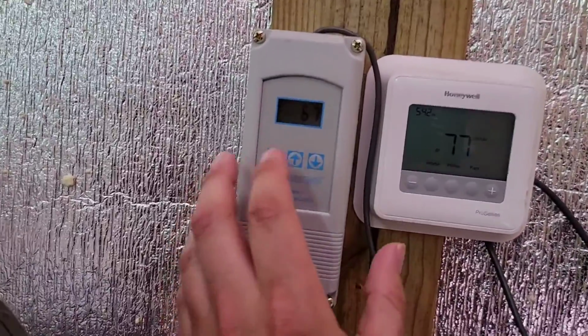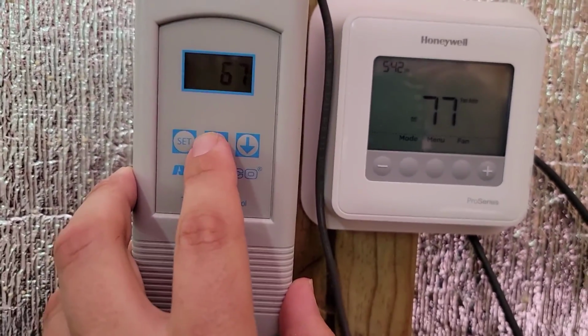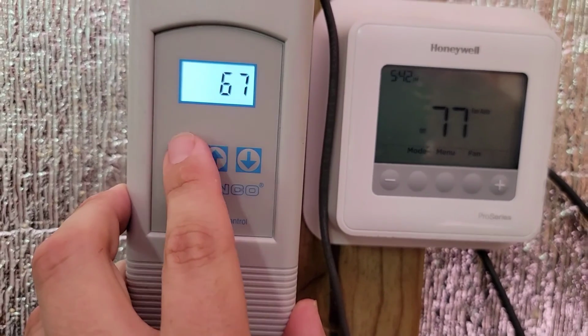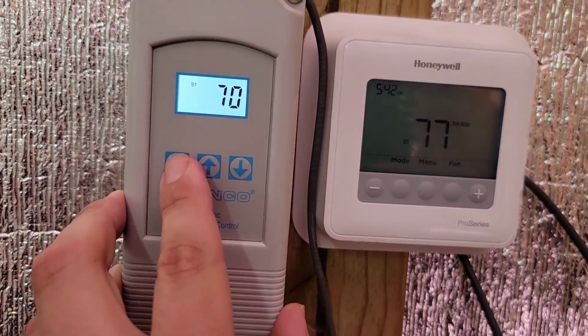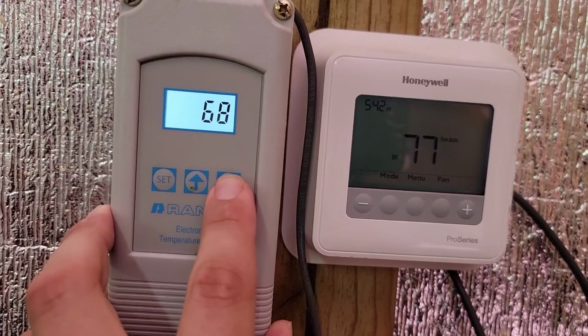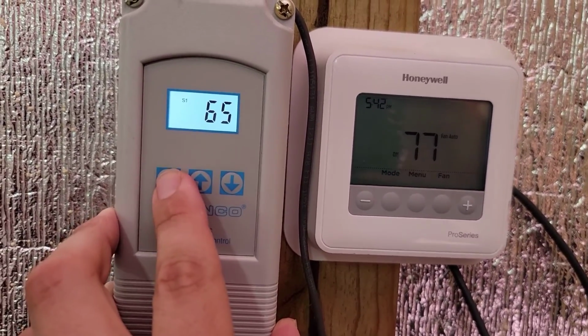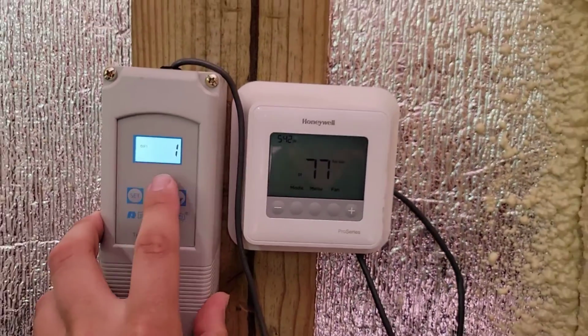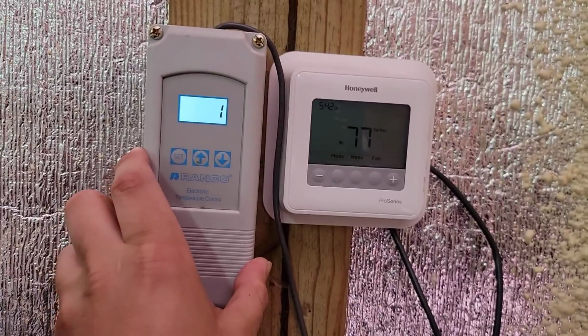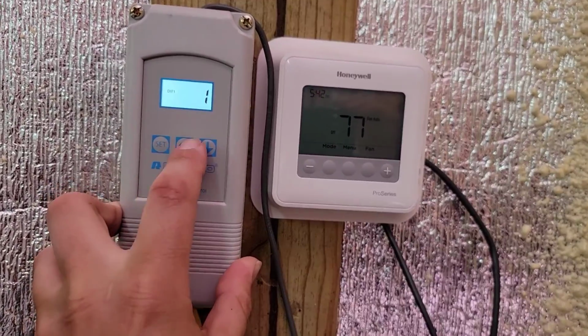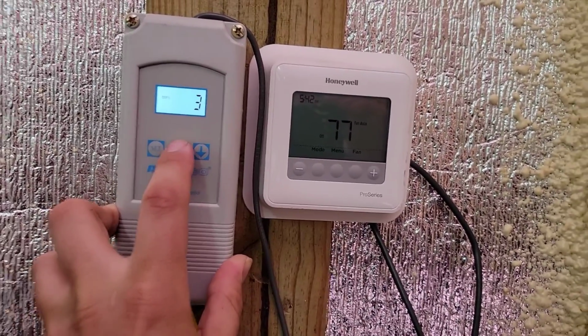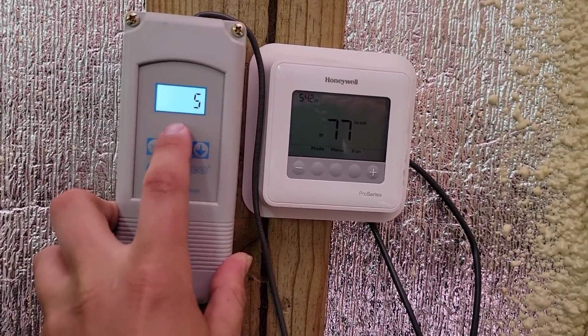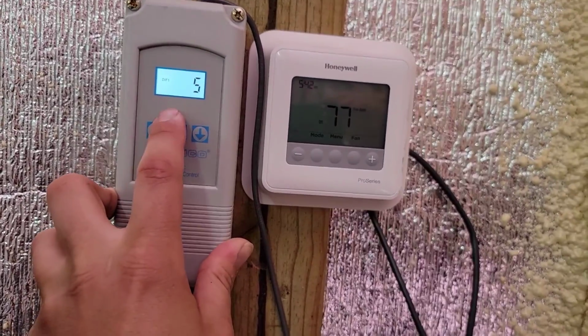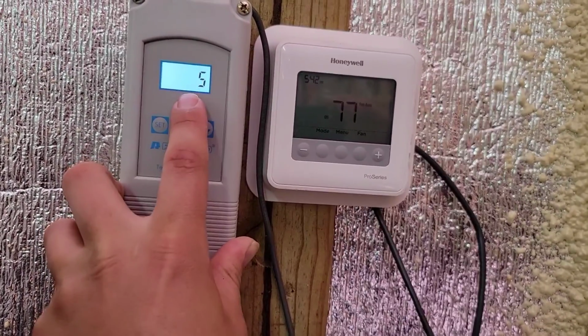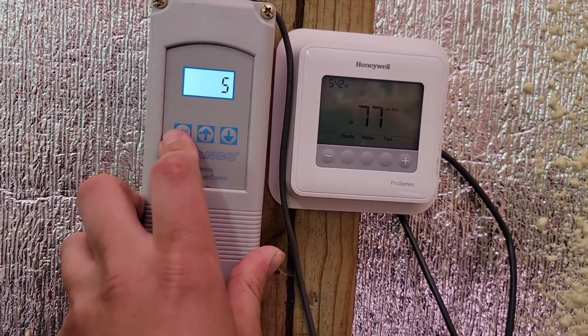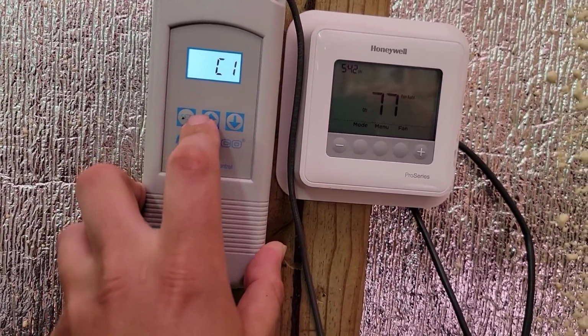All right, now for turning on the chiller, let's go through some things here. So if I push set, it shows me Fahrenheit. My set temperature, I'm going to go to 65. I'm going to go to 1 degree differential. That means that when it gets to 66, it'll turn back on. And I can set it for 3, 4, 5 degrees - that means when it gets down to 65, it shuts off, and then when it rises that many degrees, it'll turn back on and kick it back down to 65.